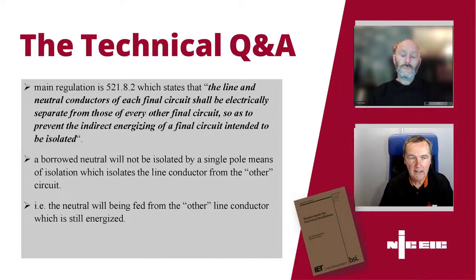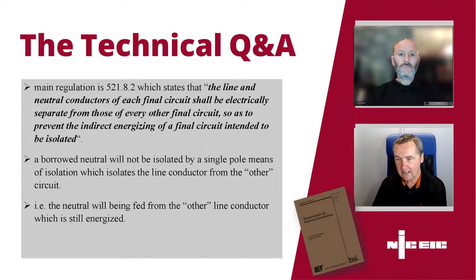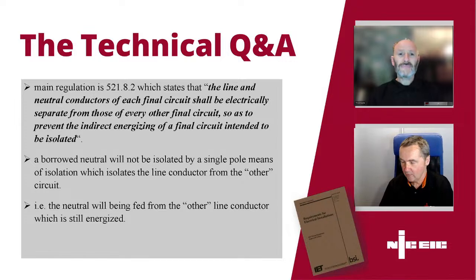So that's still considered a live conductor and therefore a potential shock risk. So you do have to ensure that it's isolated. That regulation tells us that the line and neutral conductors of each final circuit shall be electrically separate from every other final circuit, so that you can uniquely identify it and uniquely isolate it with a single protective device or a single means of isolation. So yes, very important. Often found typically on the landing light, where you've got controls upstairs and downstairs, that they've done it through a borrowed neutral.